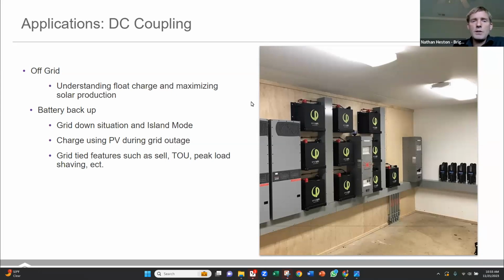And of course, you get grid tied features such as self-consumption and time of use. Time of use gives you the ability to control when you use the power that's generated from your solar array and stored in your batteries. You can also do something called peak load shaving by measuring and monitoring how much power you're pulling from the grid. If you pull beyond a certain amount, the CTs that are detecting that will be integrated into your equipment, and you can use the software of the equipment to shave off those peaks. So peak load shaving prevents you from drawing too high of a power load from the grid.